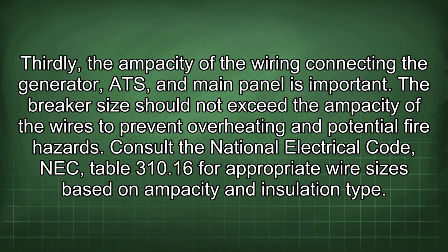Thirdly, the ampacity of the wiring connecting the generator, ATS, and main panel is important. The breaker size should not exceed the ampacity of the wires to prevent overheating and potential fire hazards. Consult the National Electrical Code, NEC, Table 310.16 for appropriate wire sizes based on ampacity and insulation type.